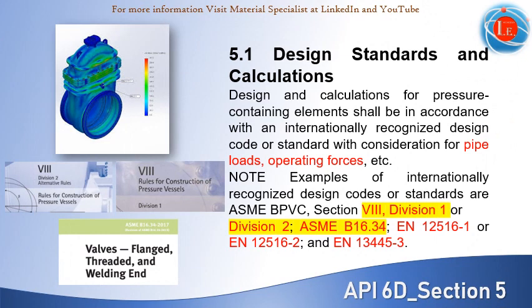Design and calculations for pressure-containing elements shall be in accordance with an internationally recognized design code or standard, with consideration for pipe loads, operating forces, etc. The most common used design codes or standards are ASME Boiler and Pressure Vessel codes. In addition, there are other European norms used as shown in this slide.